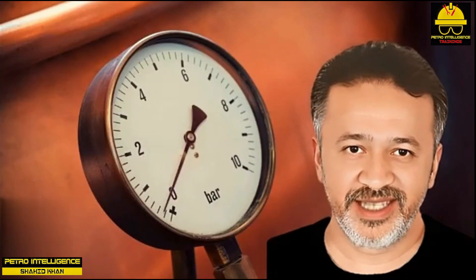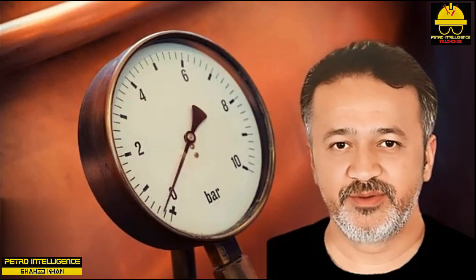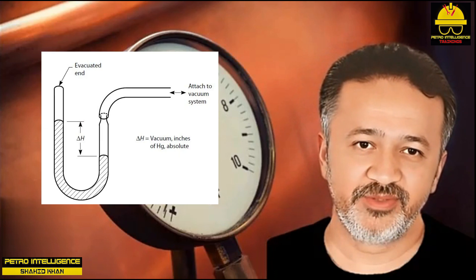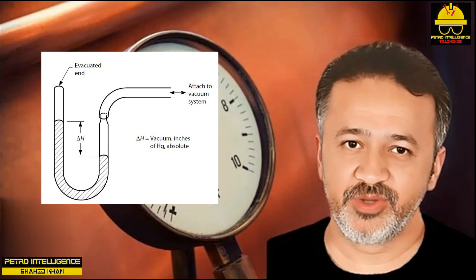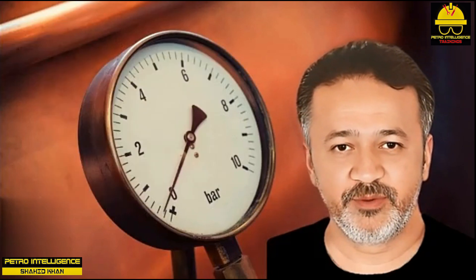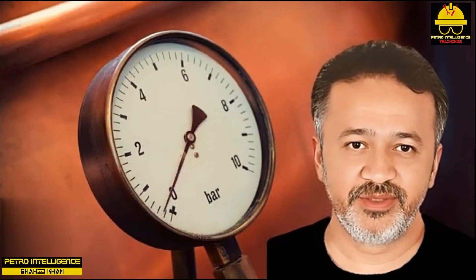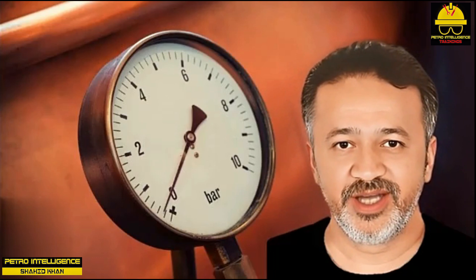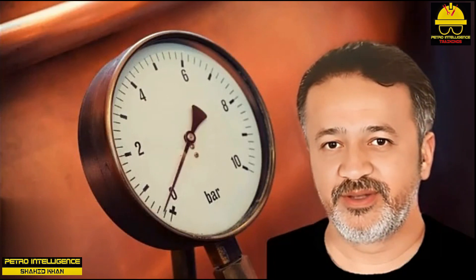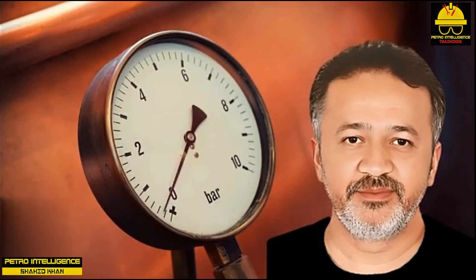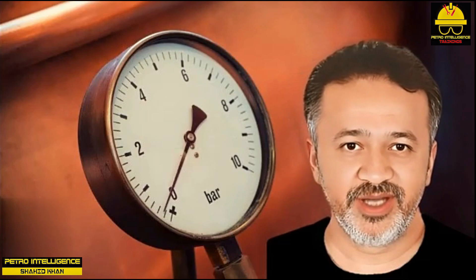The volumetric flow rate F is found by multiplying by the cross-sectional area of the orifice: F = 13.6 ft/s × 0.1 ft² = 1.36 cubic feet per second. If you measure a very small ΔP, the orifice plate hole is oversized and the recorded flow accuracy is poor. If ΔP is quite high, the orifice plate is undersized and restricting flow — and the recorded flow on the control panel may be off-scale.